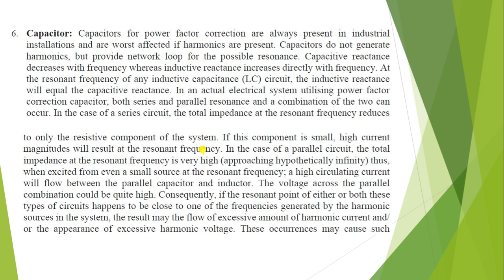The result may be the flow of an excessive amount of harmonic current and/or appearance of excessive harmonic voltage. This may cause such problems as capacitor bank failure, excessive capacitor fuse operation and dielectric breakdown of insulated cables. In most low voltage installations, the following guidelines may be applied. First, if the kVA of the harmonic generating load is less than 10% of the transformer kVA rating, capacitors can be installed without concern for resonance. Second, if the kVA of the harmonic generating load is less than 30% of the transformer kVA rating and the capacitor kVAR is less than 20% of the transformer kVA rating, capacitors can be installed without concern for resonance.